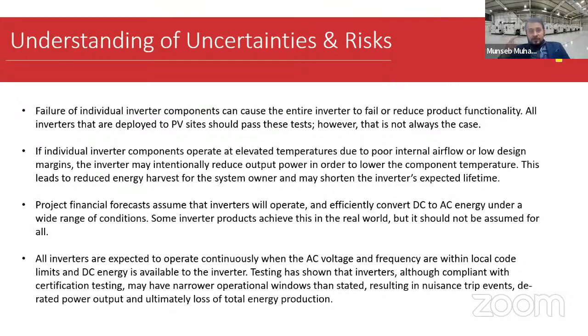So all inverters in general are expected to operate continuously when the AC voltage and the frequency are within the local code and limits, and the DC energy is available. But testing has shown that in real time the inverters have narrower operational windows than stated on the data sheets, resulting in nuisance trip events and also derated power output and ultimately lost total energy production.